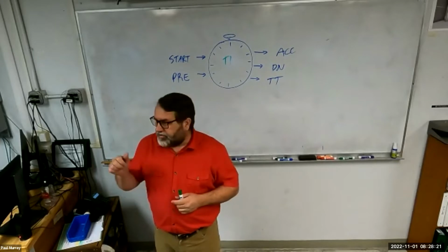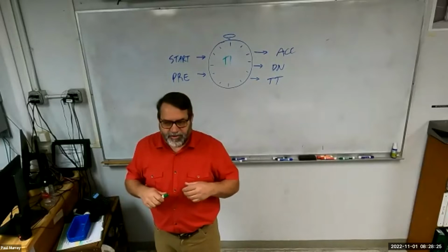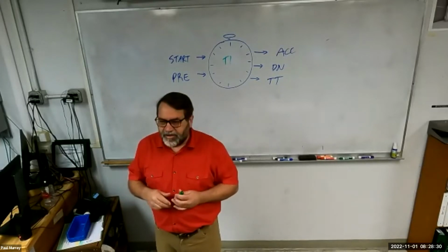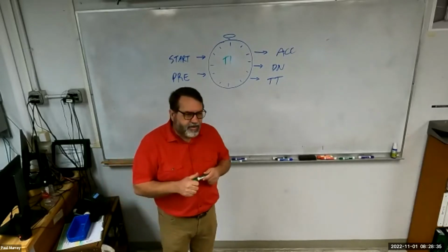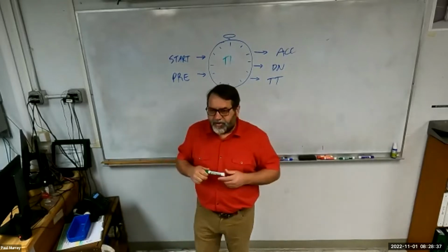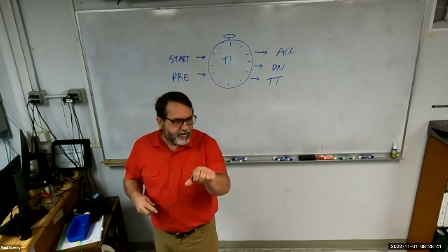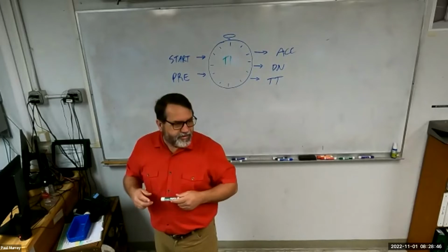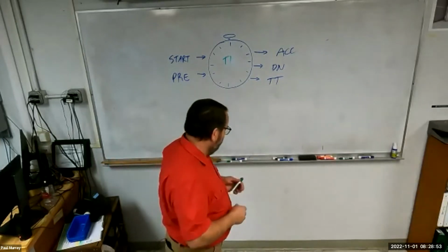If you don't hold the start button down for like a second, then the motor will try starting, but it just won't start. It needs a long, strong signal to get it started. So you could put a sign up on the control panel to tell the operators that when they start the pump, they have to hold their finger on the button for 2 seconds to make sure it starts. And is that reliable? Probably not, right? Because people are lazy.